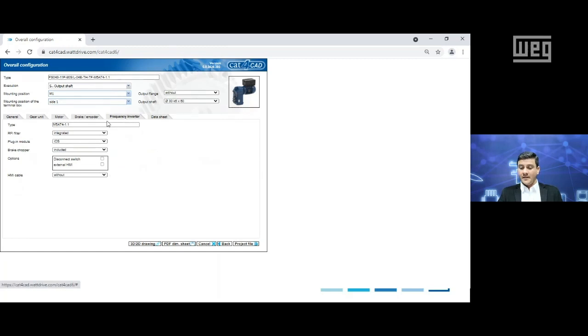For the inverter, you can also do some customization. The inverter in this case has an RFI filter integrated. The plug-in module, you can select from different options, and this is about the number of I/Os that the inverter will have built in. So if you need extra built-in I/Os, digital or analog outputs, or maybe some bus communication, then you can select from this field. Okay, the brake chopper for the VSD in this case is already included.